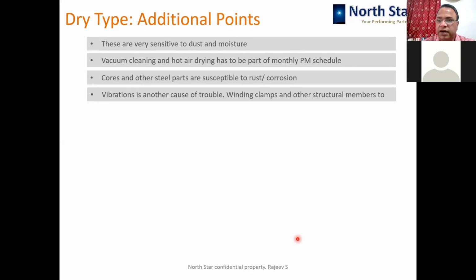Then dry type transformers are very susceptible to vibrations because there is no damping material like oil. So the impact of the looseness comes on the winding, and as a result many times your conductors and contacts become loose and you get all related issues like poor contact, high contact resistance, arcing over, just because of vibrations.